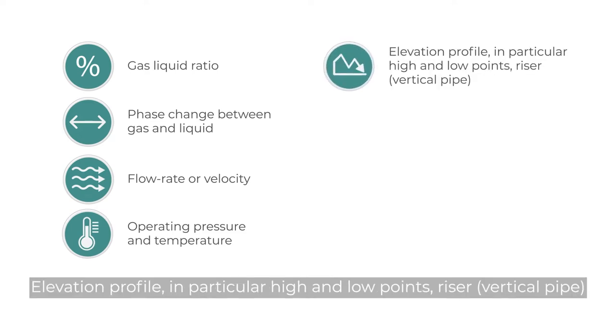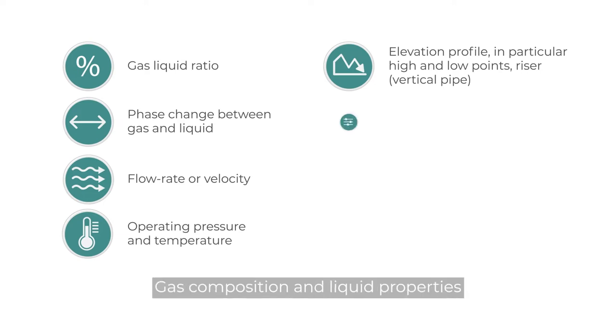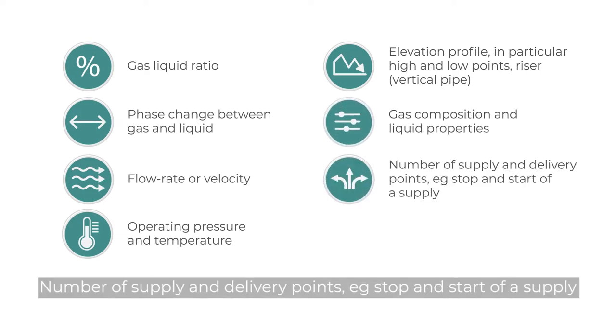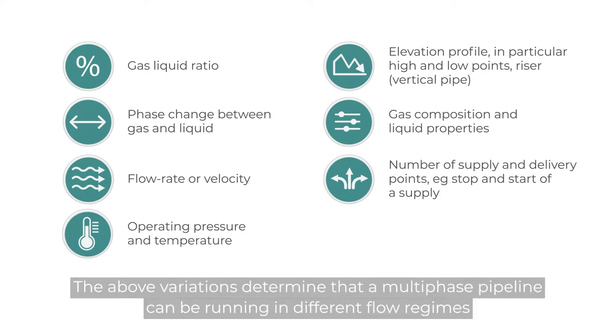Gas-liquid ratio, phase change between gas and liquid, flow rate or velocity, operating pressure and temperature, elevation profile, in particular high and low points and risers, gas composition and liquid properties, and number of supply and delivery points. The above variations determine that a multi-phase pipeline can be running in different flow regimes.